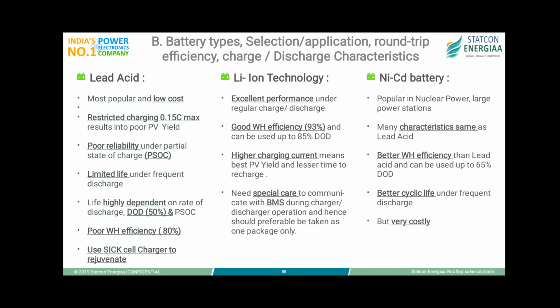It suffers from problems of PSOC. If your battery is not taken care of very well, you're really compromising, and best of luck for such installations, because all claims of 5 years will fall flat—you may end up replacing batteries even after the second year. It has limited life, so you have to discharge your batteries very judiciously. You cannot go for off-grid systems this way. DODs you can opt for are a maximum of 50%.